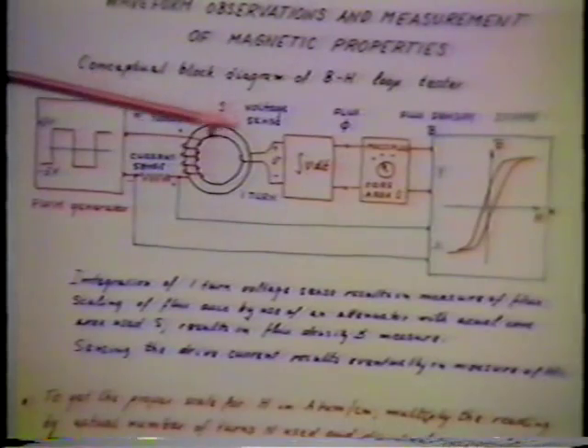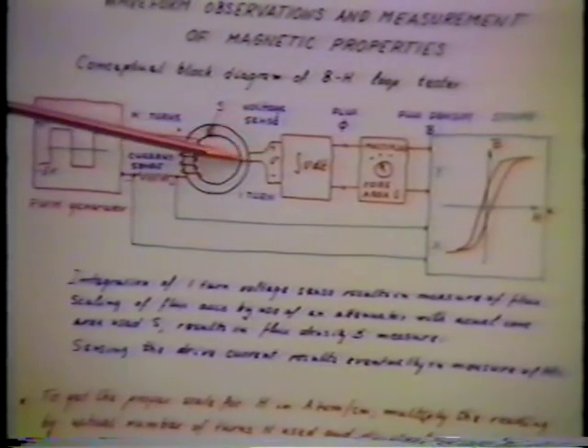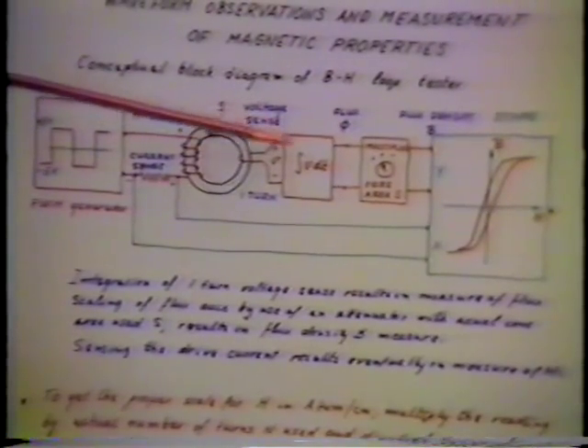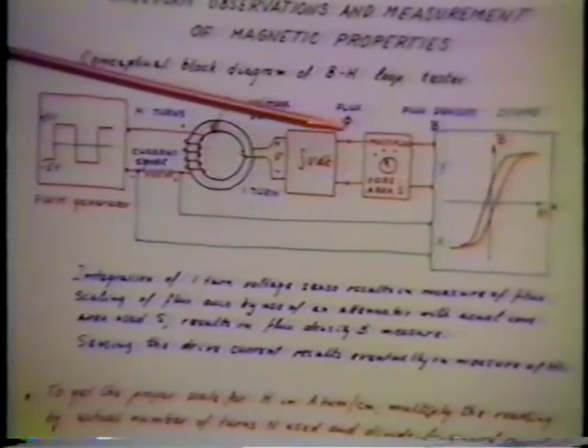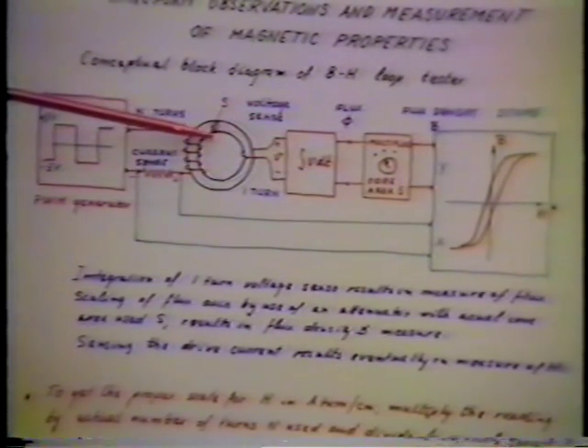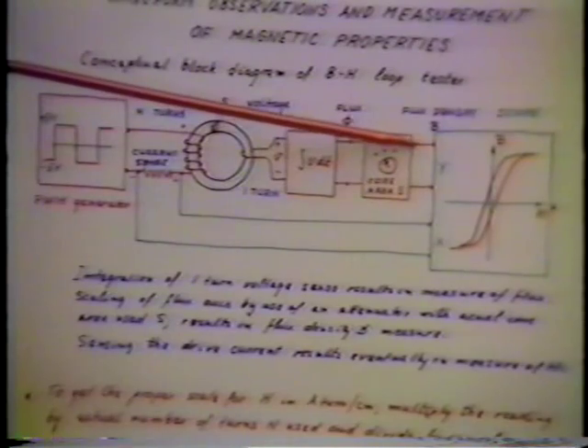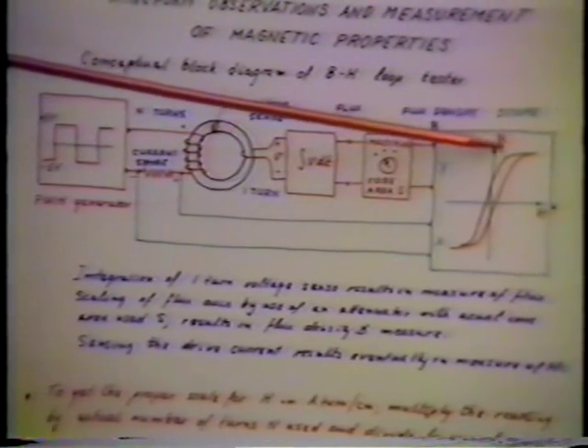Then, in order to sense the flux, we use voltage sense winding, one-turn winding, and by separate box which integrates that volt seconds, we are assessing the flux. And if we dial the core cross-section area of the core, we can essentially divide that flux with the cross-section of the core and get the reading of the flux density.